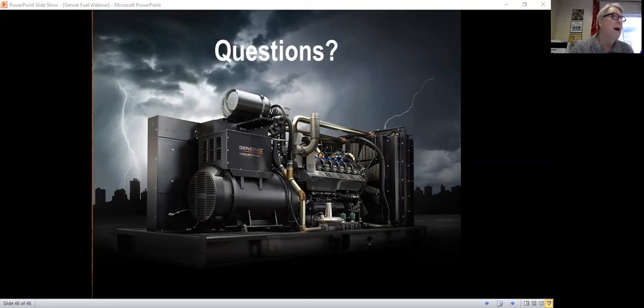So I'd much rather buy the 480 volt generator and put in a transformer to step up to 13.8. Then anybody can work on it because they're used to 480 volts, and it costs a lot less. Transformers are extremely reliable, and a 13.8 kV alternator, if you have problems with that, is much more difficult to repair than a 480 volt alternator. So the answer is yes, it's available - no, I wouldn't recommend it.